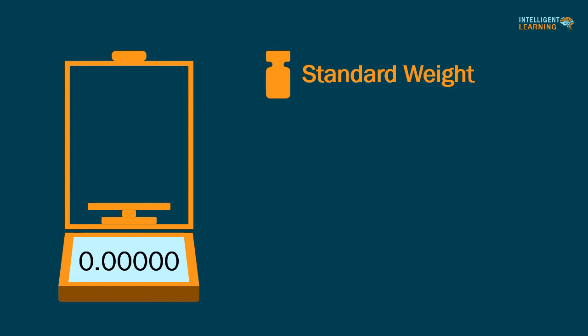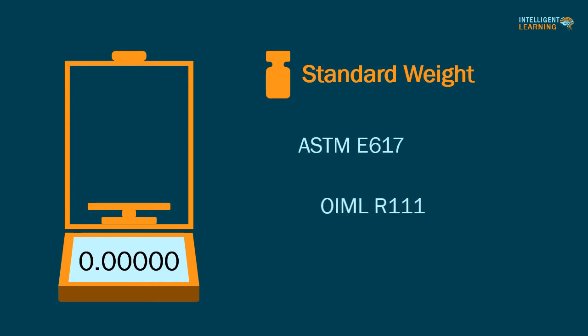Standard weights should be certified as per the guidelines of the American Society for Testing and Materials (ASTM) E617, or the International Organization of Legal Metrology (OIML) R111.